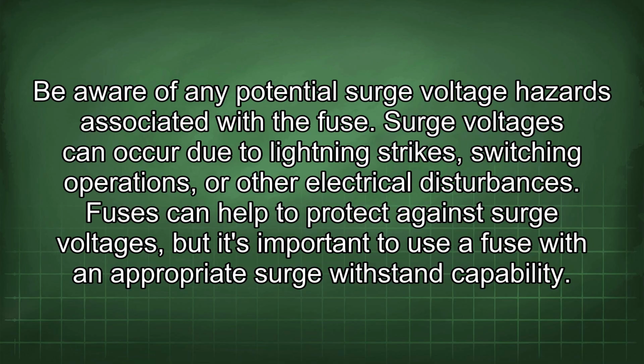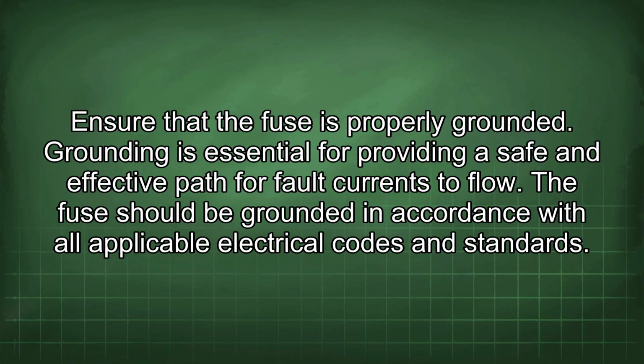Be aware of any potential surge voltage hazards associated with the fuse. Surge voltages can occur due to lightning strikes, switching operations, or other electrical disturbances. Fuses can help to protect against surge voltages, but it's important to use a fuse with an appropriate surge withstand capability. Ensure that the fuse is properly grounded. Grounding is essential for providing a safe and effective path for fault currents to flow. The fuse should be grounded in accordance with all applicable electrical codes and standards.